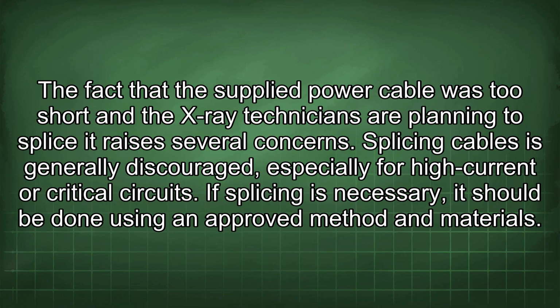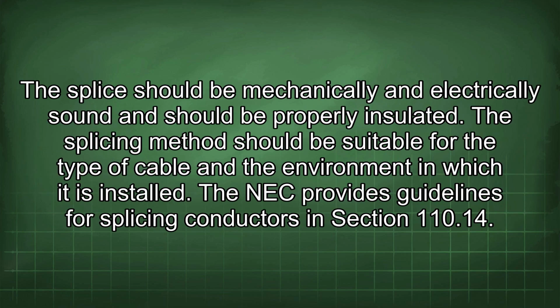The fact that the supplied power cable was too short and the X-ray technicians are planning to splice it raises several concerns. Splicing cables is generally discouraged, especially for high current or critical circuits. If splicing is necessary, it should be done using an approved method and materials. The splice should be mechanically and electrically sound and should be properly insulated. The splicing method should be suitable for the type of cable and the environment in which it is installed. The NEC provides guidelines for splicing conductors in section 110.14.